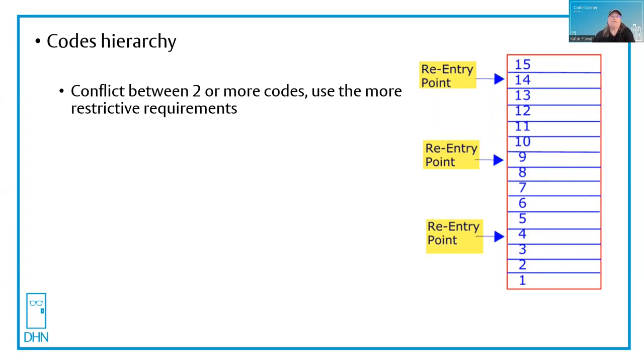the doors can be unlocked simultaneously using fail-safe positive latching devices. In NFPA 101, the Life Safety Code, they have those same two provisions but they also allow you to mechanically lock the doors as long as on every fifth level there's a way to re-enter from the stair side.